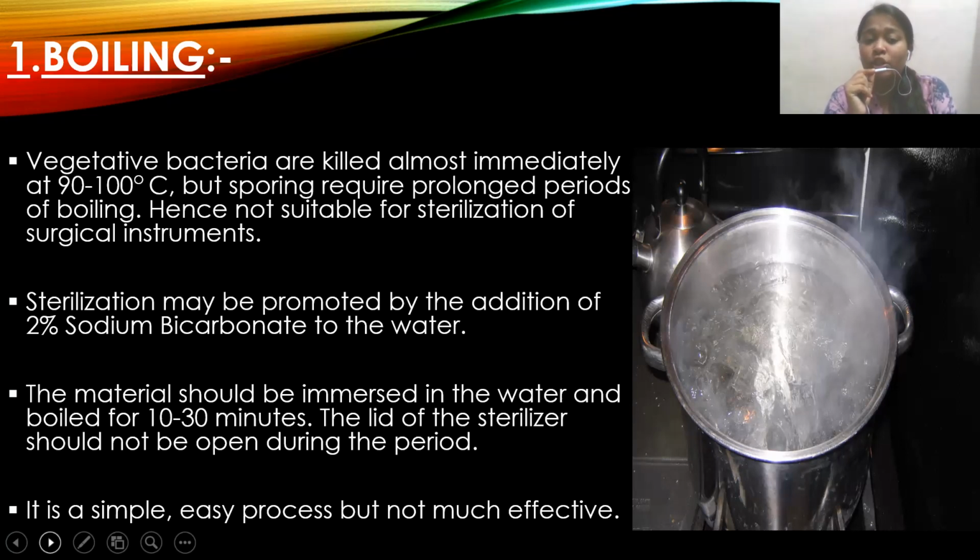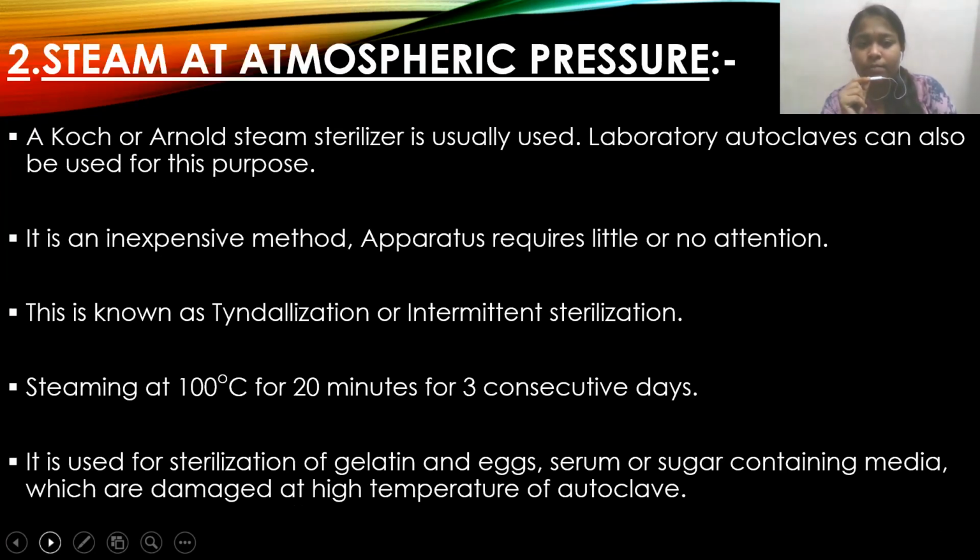If you want sterilization to be more effective, then add 2% sodium bicarbonate to the water. The material should be immersed in water and boiled for 10 to 30 minutes. The lid of the sterilizer should not be opened during this period. It is a simple, easy process, but not much effective, as it does not sterilize surgical instruments, which is important to sterilize.